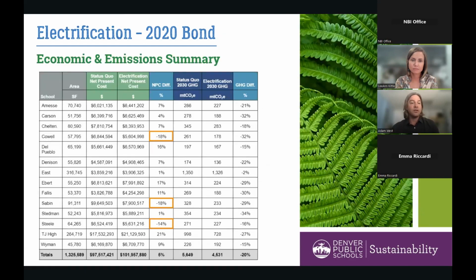Breaking that down a little more, here are all 14 schools that were getting cooling. We looked at what would be the status quo mechanical system to add cooling, versus what it would cost to electrify those systems, largely looking at heat pumps. You can see the net present cost difference, in some cases actually lower than the status quo, largely due to savings on mechanical equipment like chilled water piping and chillers. In other cases, like East or Stedman, it might be cost neutral.